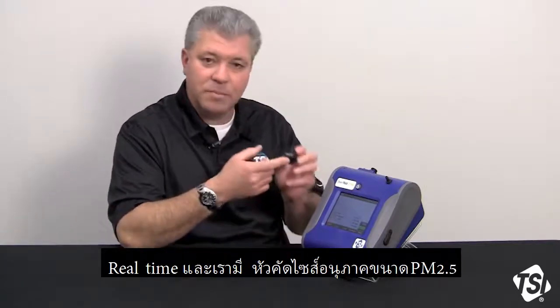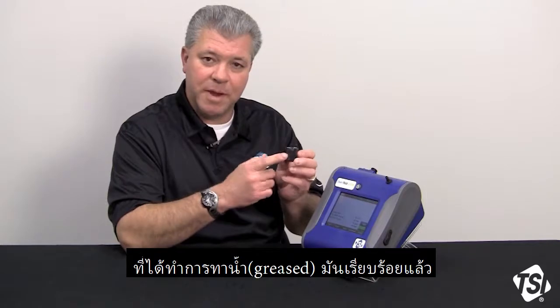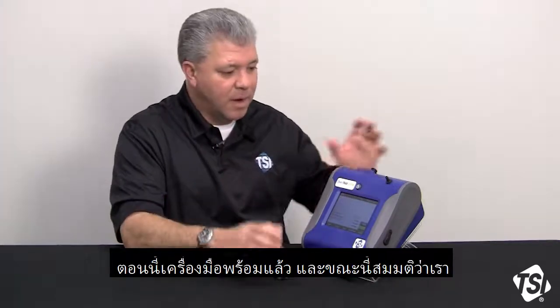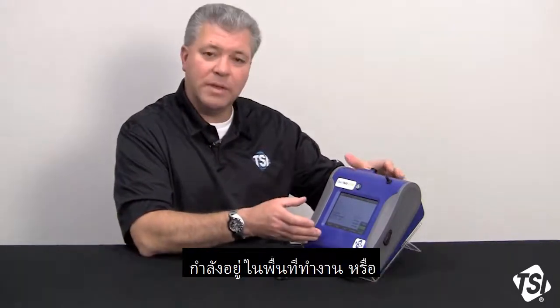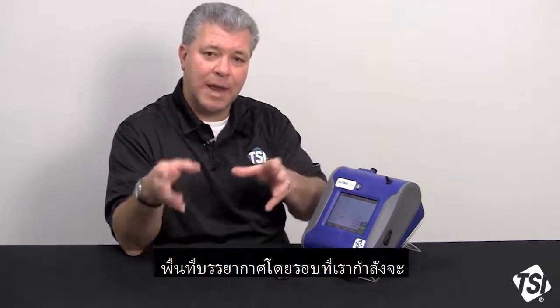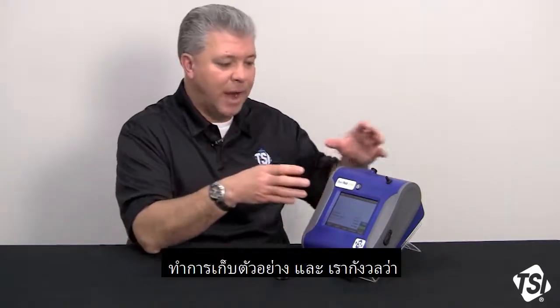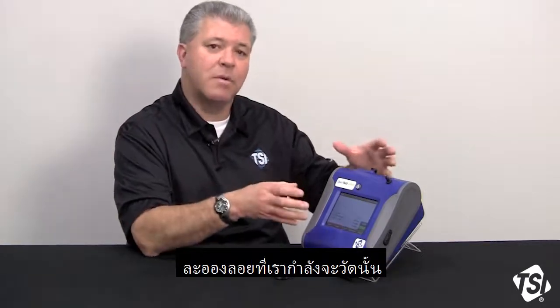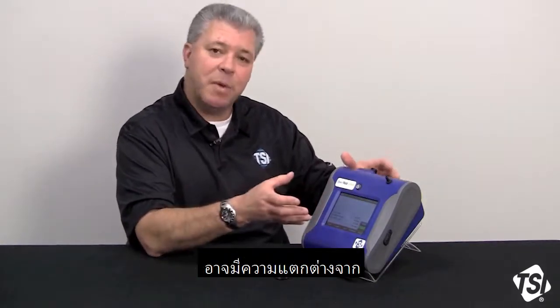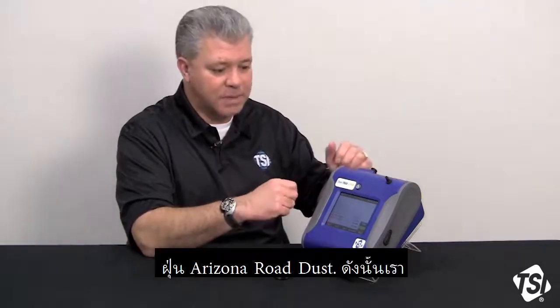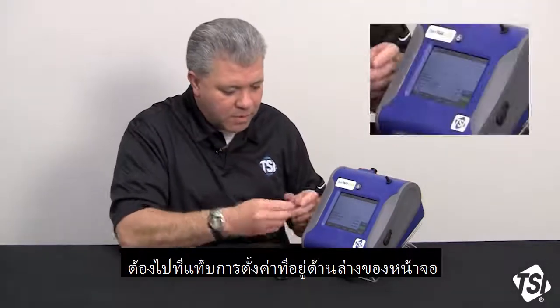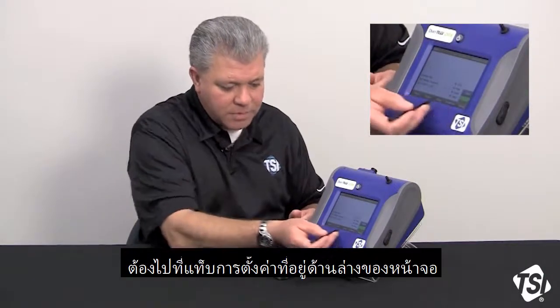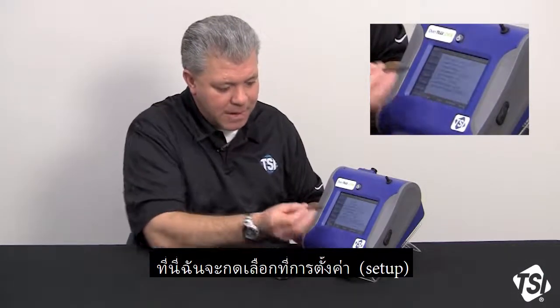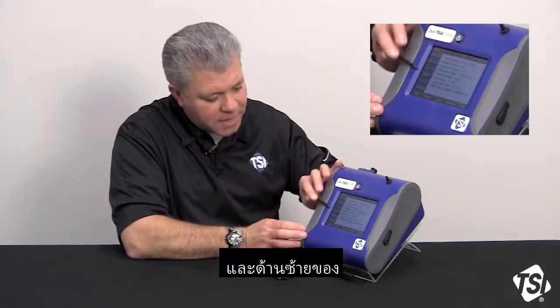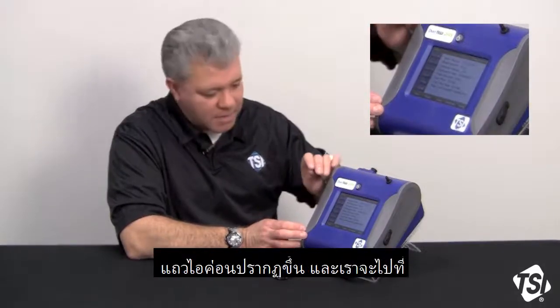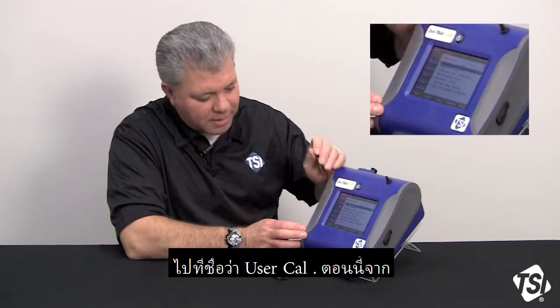And we have a PM 2.5 impactor that has been greased up already. It's ready to go. And now let's assume we're doing this in the work area or the ambient area that we're going to do our sampling. And we're concerned that the aerosol we're going to measure may be different in response than the Arizona road dust, the A1 test dust. So we're going to utilize the lower setup screen here. I'm going to press the setup tab. And across the left side of the instrument, we're going to see another row of icons come up. And we're going to go to the user cal icon.